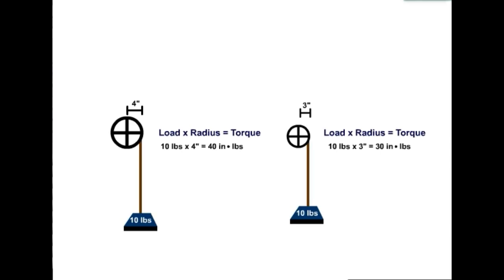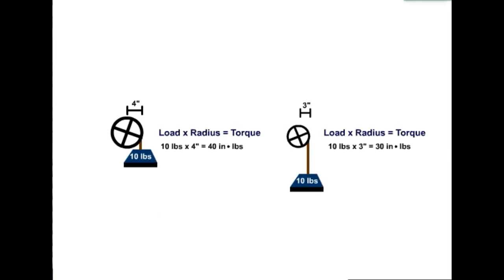Hydraulic motors are rated according to displacement and torque. The first consideration should be torque. Hydraulic motors are rated in foot or inch pounds of torque per given PSI, typically in pounds per 100 PSI. Torque is equal to load times radius. Large displacement motors usually have a greater radius for the hydraulic fluid to push against. Therefore, they create more torque at a specific pressure.